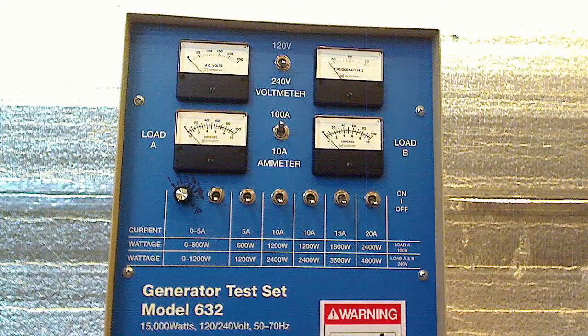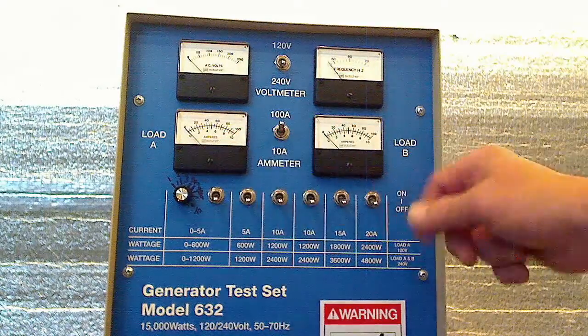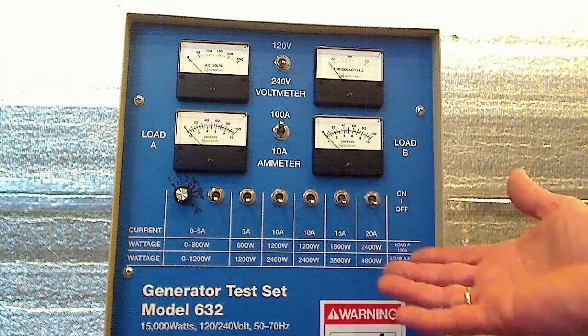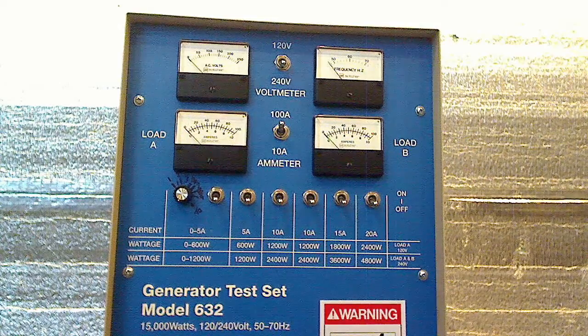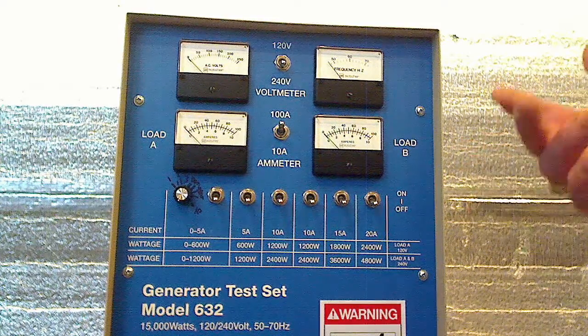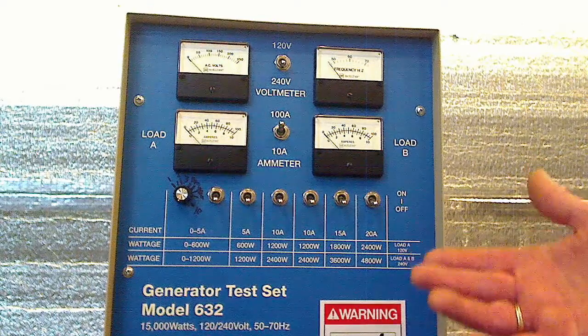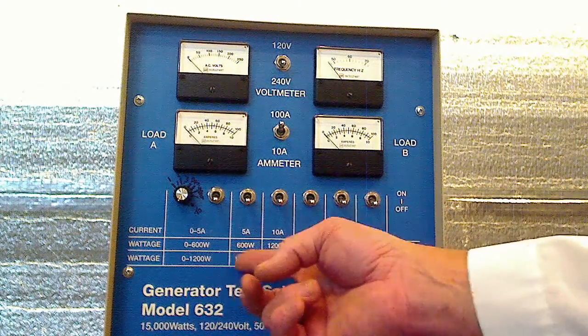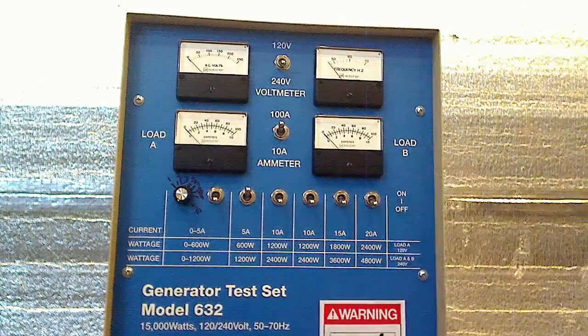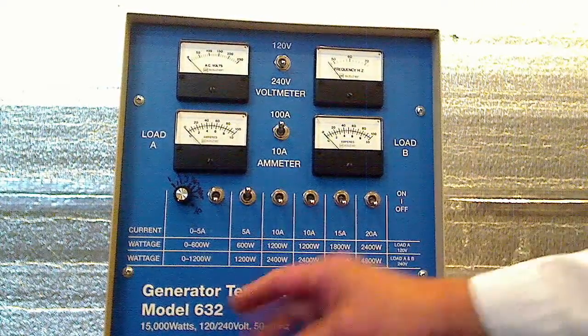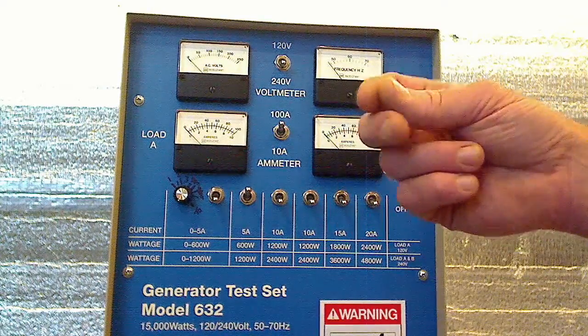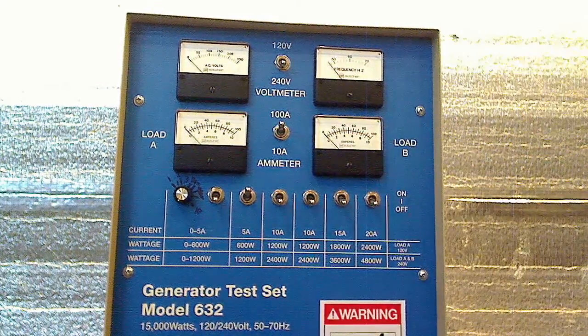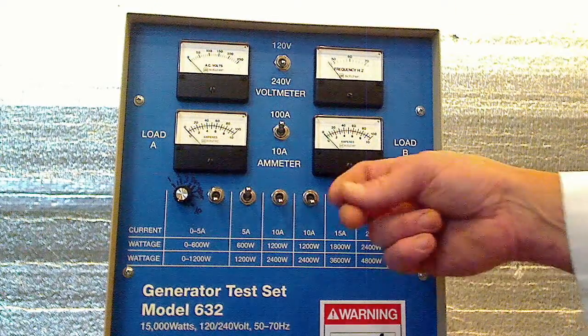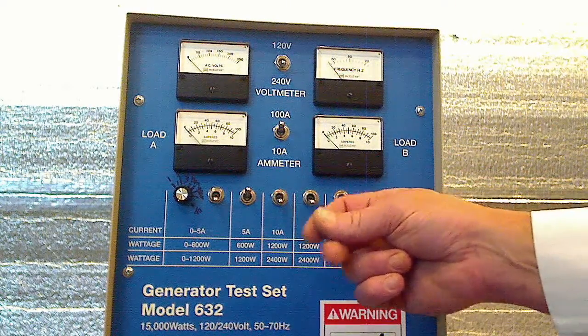Let's go over to the load bank. This load bank has switches that let us test a 12 to 15K generator. So when setting the load block on a unit, we start off with the lowest setting, 1200 watts. If it's a 7,000 watt generator, we'll put 1200 on it, run it to the rich side immediately, then run it lean until it stumbles, start running it a little rich, and hold it there.